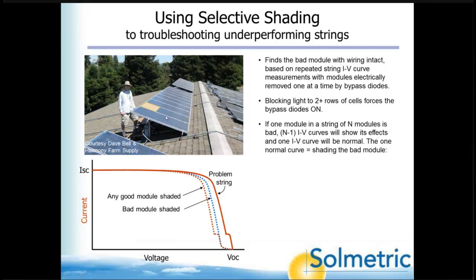So that's the method. If you put the cardboard over a non-problem module, you'll still have the problem in the string IV curve. So a way of looking at that in terms of IV curves themselves is to look at this graph at the bottom. And our very first measurement of the string, which exposes the problem, is the solid red curve. And we see that we have a little step at the bottom, which is typically 10 or 12 volts wide, which means that our max power point is going to be shifted to the left 10 or 12 volts. So we'd like to find out what that is, because that's costing us money.